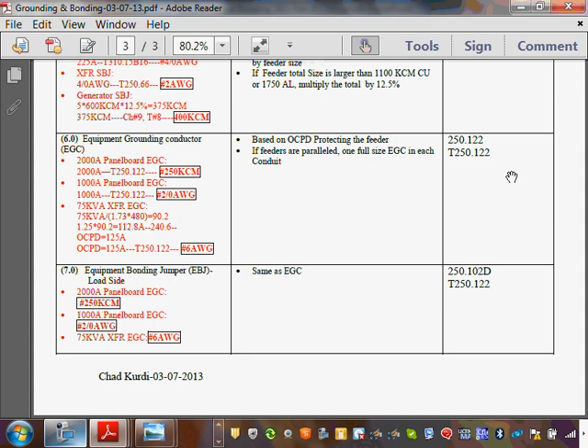The only time it becomes an issue is if your voltage system is 480/277, and you are encountering eccentric or concentric knockouts, then you have multiple other options. You have to have ground bushings on it, or the conduit has to match the hole. Any comments, guys, about 6.0 and 7.0? So that's equipment grounding conductor.